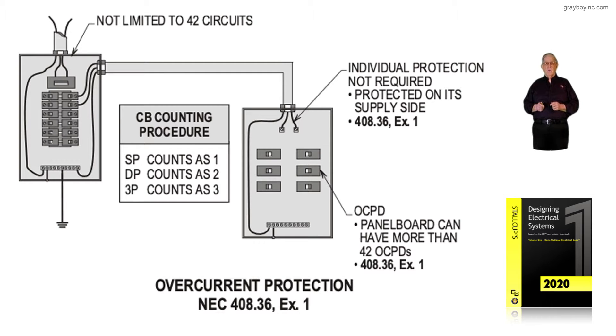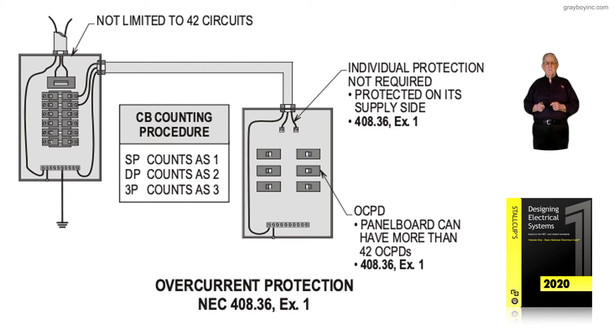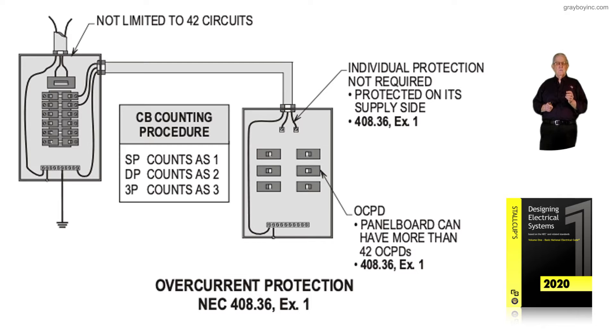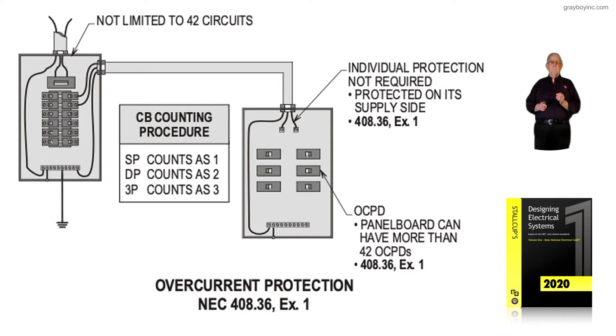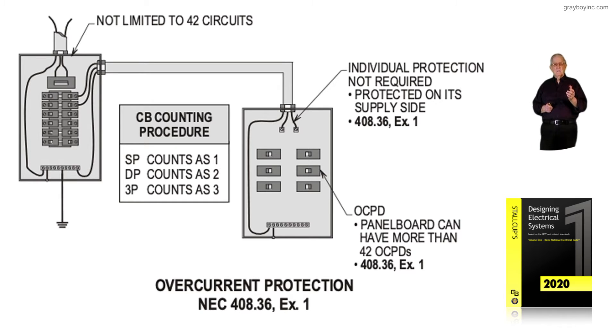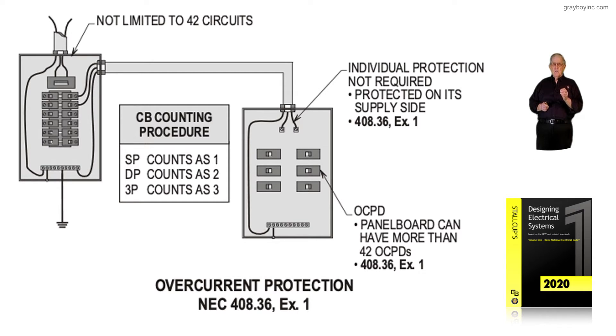This figure deals with overcurrent protection when Exception 1 to 408.36 is being applied. Notice in the service equipment to the left, we're not limited to 42 circuits. By the rules that changed in a couple of editions of the code in the past, we could have an 800-amp main there and have as many as 80 to 100-amp overcurrent devices below it — you weren't restricted to 42 circuits.